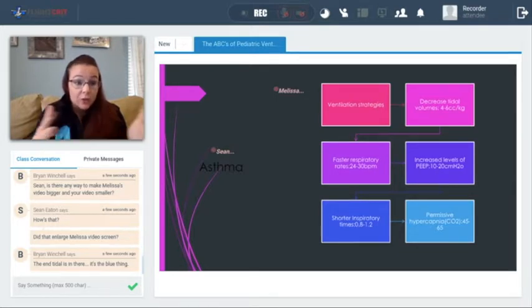But here's what I see. I see a lot of people flip that over and they're like, well, I don't want above 30. So I'm going to put 30 over 5 or 25 over 5. You're not going to be getting tidal volumes. Your kid's going to automatically start air trapping, and their numbers are going to start skyrocketing. So I see people not pick aggressive enough pressure control settings.